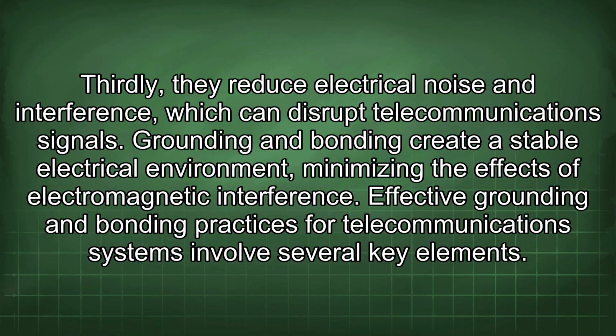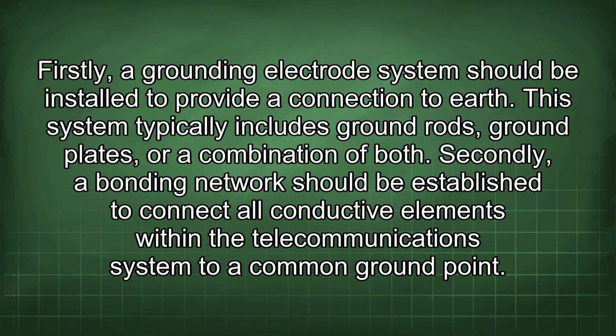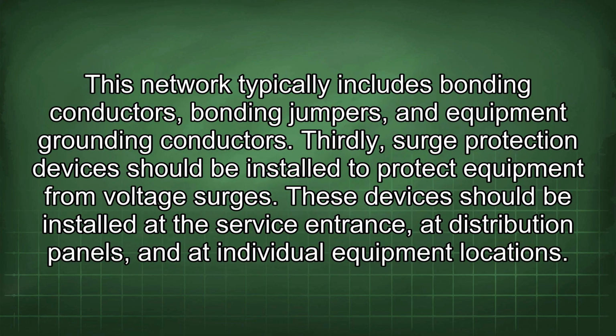Effective grounding and bonding practices for telecommunications systems involve several key elements. Firstly, a grounding electrode system should be installed to provide a connection to Earth. This system typically includes ground rods, ground plates, or a combination of both. Secondly, a bonding network should be established to connect all conductive elements within the telecommunications system to a common ground point. This network typically includes bonding conductors, bonding jumpers, and equipment grounding conductors.